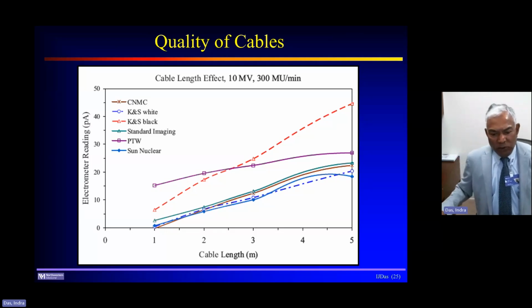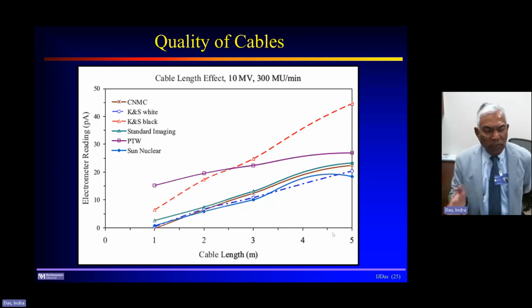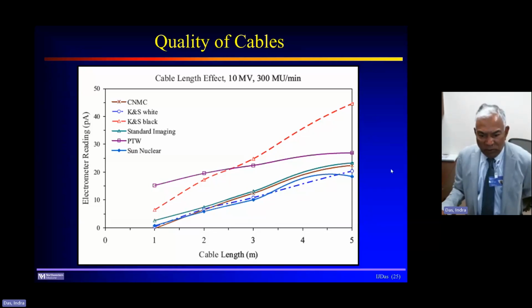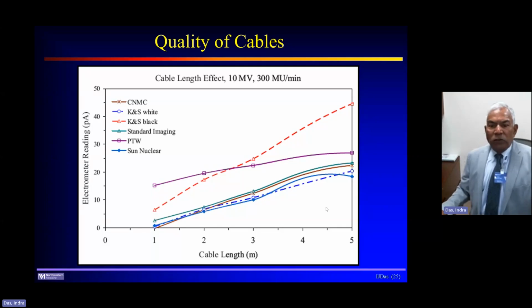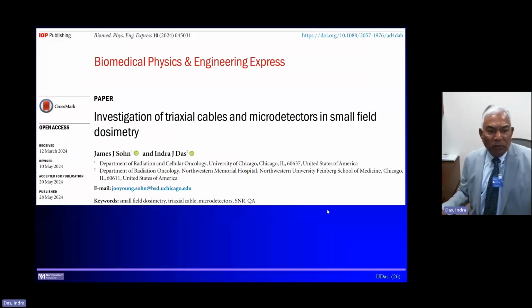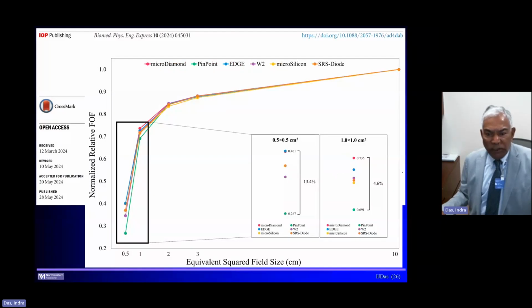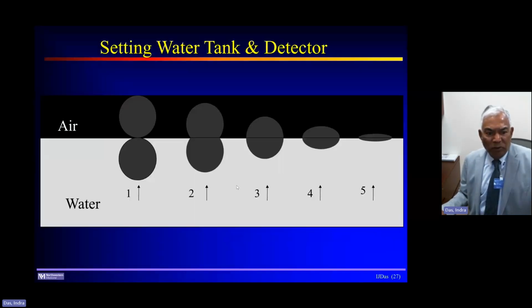The length of the cable also is a problem if you increase the number. So try to minimize the length of cable, because depending upon the quality of the cables, you can see that your readings are going to be dependent on the length of the cable when you have it in the beam. So that's another criterion. We just wrote this paper about the investigation of triaxial cables, especially for small fields, because you know that the signal is very small, and when you have poor cables, then it just overwhelms the signal to noise ratio, and it becomes an issue. And especially if you see here that for small fields in this region, depending upon the cables and combination of the detectors, you can have very, very large differences in your signal. So you have to be careful.